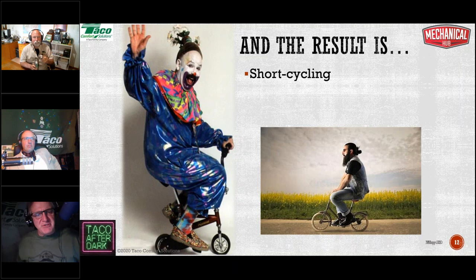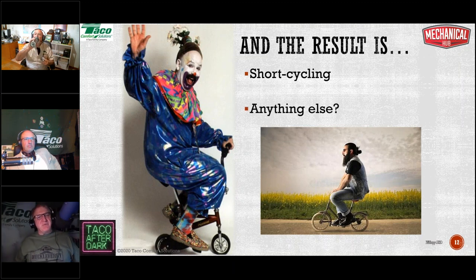What happens when it's 50% load out? And it's 35,000 BTUs instead of 70,000 BTUs. I'm still pumping 9.5 GPM, man. So now the best delta T I'm going to see is between 5 and 7 degrees. And that's a 50% load, right?